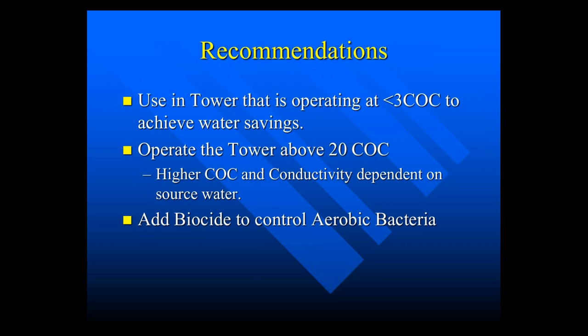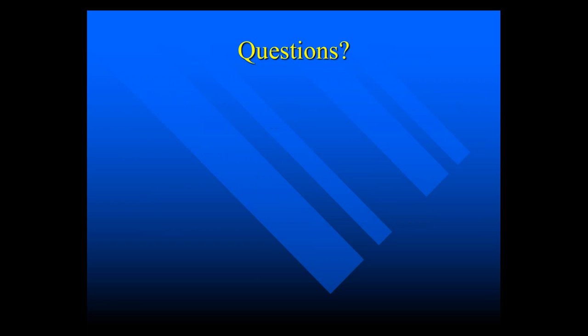My recommendations for this system: use it in a tower that's currently operating at less than three cycles of concentration to achieve the greatest water savings. Operate the tower above 20 cycles of concentration, and at higher cycles and conductivity depending on the water source, but add biocide to control aerobic bacteria. Don't cycle it up to 100 or 200 cycles of concentration just to try to achieve biological control.